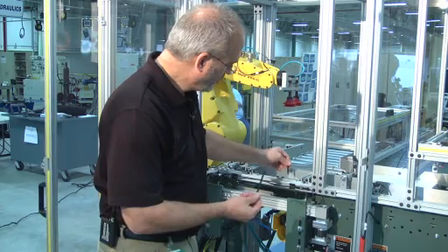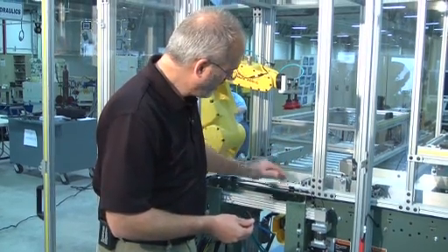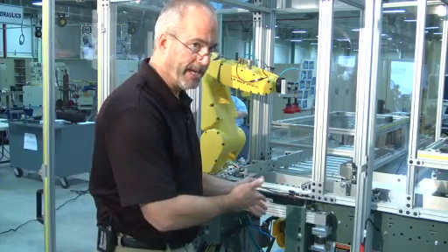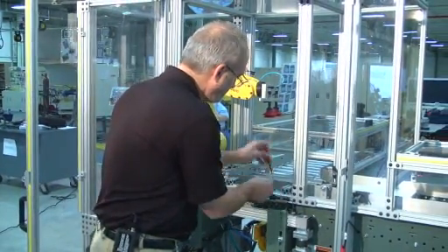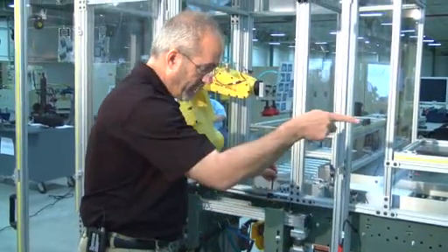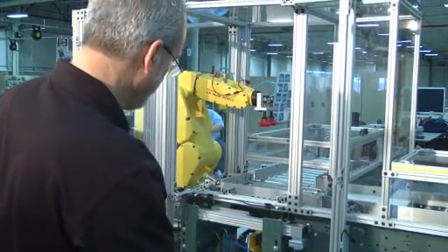And that is these loose screws, which can be put into a different location, causing a mechanical fault with the servo. So the servo will actually bump into the screw and fault out. Not obvious when you look at it. Okay, so we have that not only here, but we also have it on the unload end for the pneumatic pusher, which I'll get to in a second here.